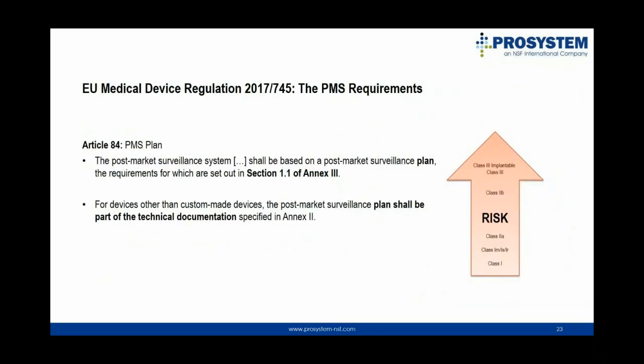So as mentioned before, Article 84 asks manufacturers to put up a PMS plan and to make it a part of the technical documentation. When creating the plan, remember that the PMS activities shall be proportionate to the risk class of the device and appropriate for the type of device. Details regarding the planning of the PMS activities can be found in the new Annex 3.